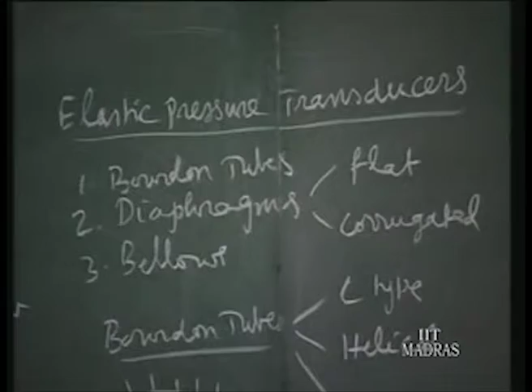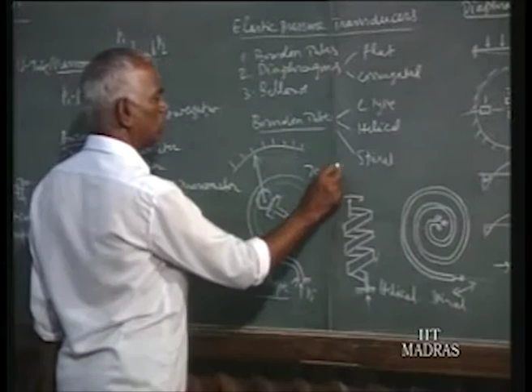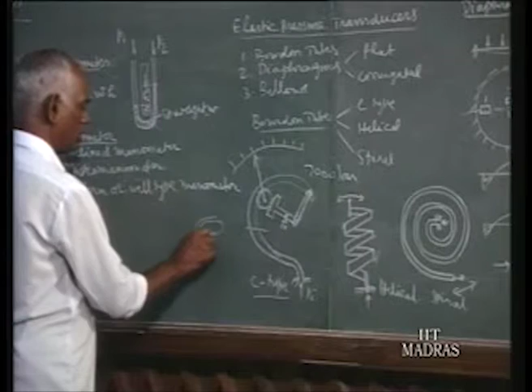And the Bourdon tube, which we have seen in one of the introductory classes, is of three types: C type, helical type and spiral type, and we can measure up to 7000 bar with any one of these Bourdon tubes. The principle is, if you take the cross section, it is an oval cross section. This is the material, and the liquid pressure is allowed inside. As the pressure increases, it will assume more or less a circular cross section. In the process, the free end makes a motion.